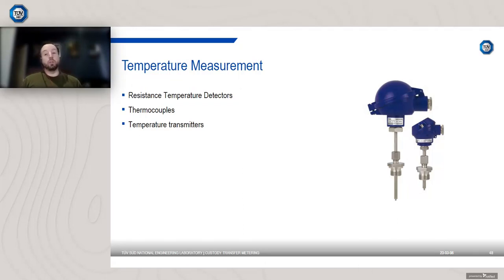Temperature measurement is another critical component. Again, it's really important for calculating things like fluid properties. It's also important for accounting for things like thermal expansion. So again, orifice metering, it's quite important you get the dimensions of the orifice plate measured to a low uncertainty, but changes in temperature will cause thermal expansion on the pipe. So how do you account for that? Well, you need to measure the temperature.